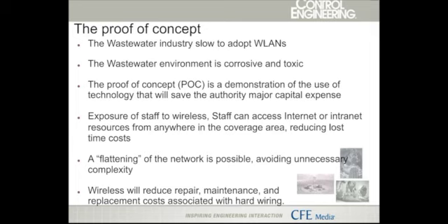So the proof of concept was done for several reasons other than what I've just explained. The wastewater industry, the water industry, is very slow to adopt wireless technology. There's a lot of reasons for this. One of the reasons is that the environment is corrosive and toxic, and the wireless equipment available was not of such construction at that point. In other words, the enclosures would not stand up to the abuse.